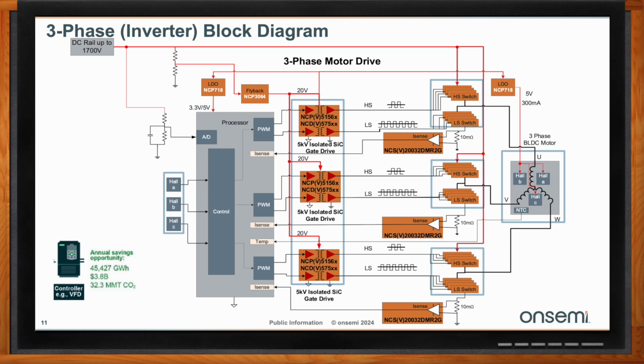There's a high side, low side switch for the U, for the V, for the W, for a total of 6 switches. Now, I have 4 switches in parallel for each of those switches, so there's really 24 in here. I'm just doing that to illustrate that for really high power motors, you may want to put these switches in parallel, which helps reduce the RDS on.